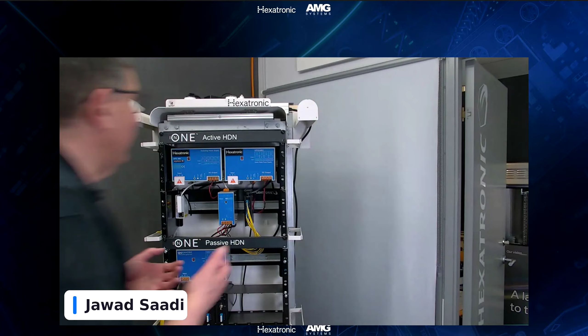We have 230 volts AC coming into this rectifier, and we get 110 volts DC. The reason we're using the 110 volts standard is that it's used in many industries, like rail as well, because the European safety standard stipulates that anything below 120 volts DC is considered ultra low voltage, which makes it touch safe and does not require a certified electrician.